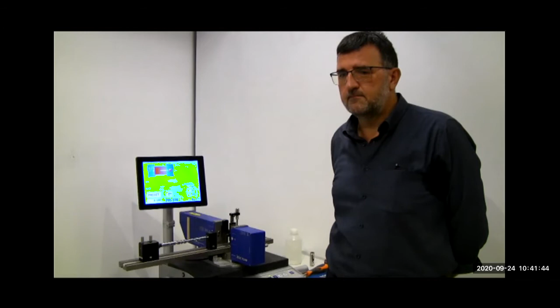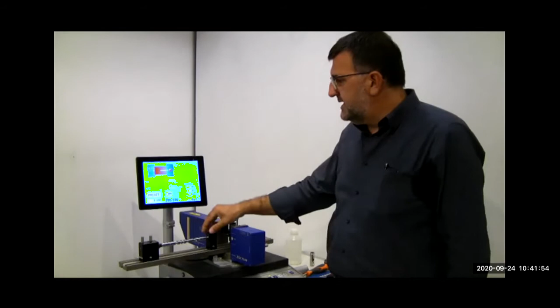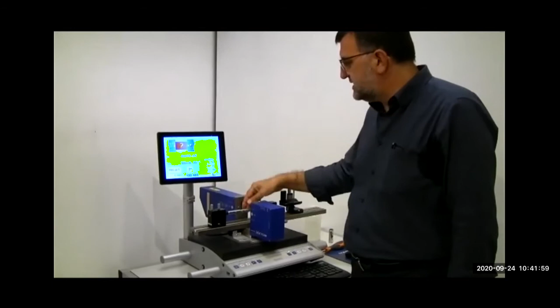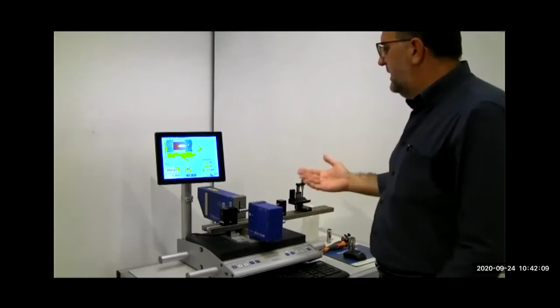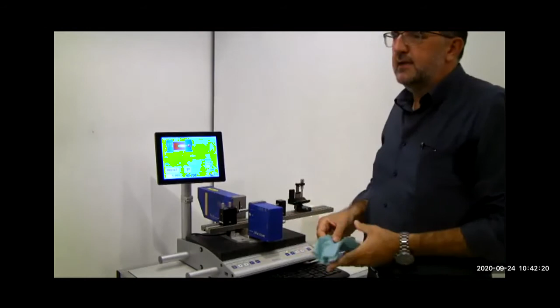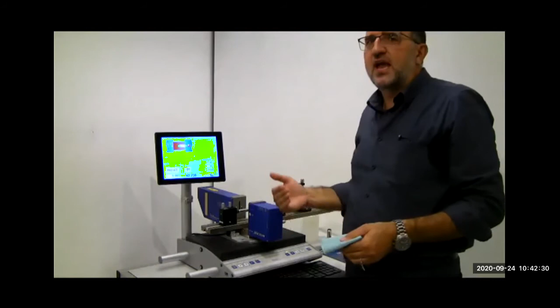How is the gauge and the measurement affected by coolant and temperature? This is a type of optic measurement, so if there is dirt on the surface of the product, I measure the object but also the dirt. Normally, in the benchtop application, the product will simply be cleaned before the measurement. This type of dirt problem may occur in some inline applications, like after a grinder machine, where we check 100% of the product that comes out from a centerless grinder machine.